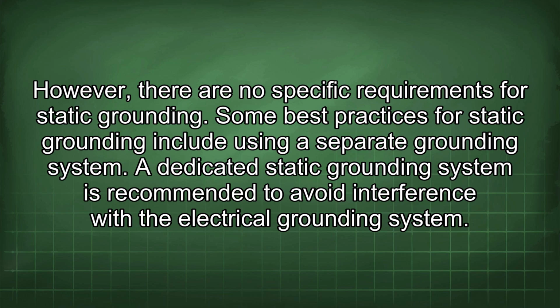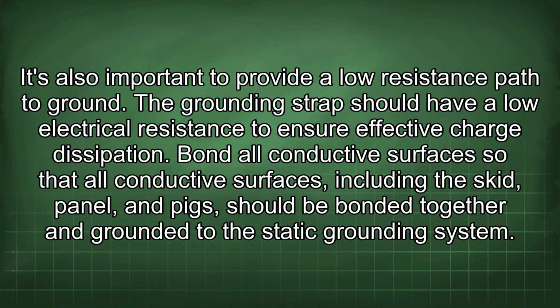Some best practices for static grounding include using a separate grounding system. A dedicated static grounding system is recommended to avoid interference with the electrical grounding system. It's also important to provide a low resistance path to ground. The grounding strap should have a low electrical resistance to ensure effective charge dissipation. Bond all conductive surfaces, so that all conductive surfaces, including the skid, panel, and pigs, are bonded together and grounded to the static grounding system.